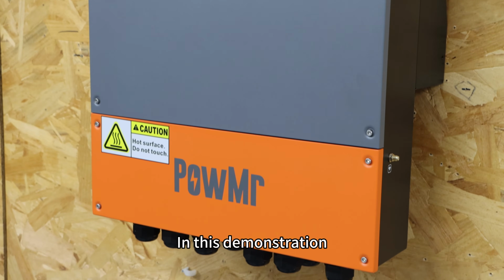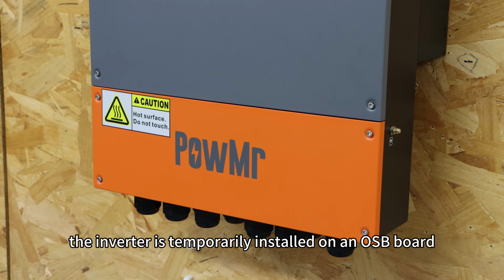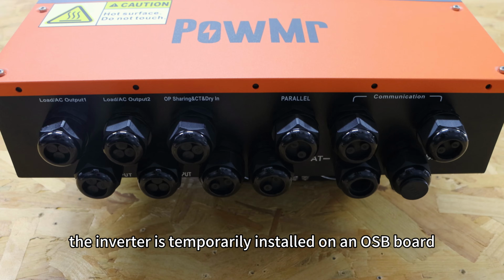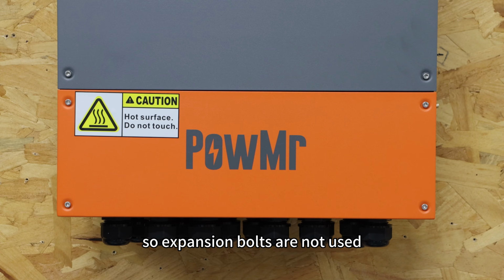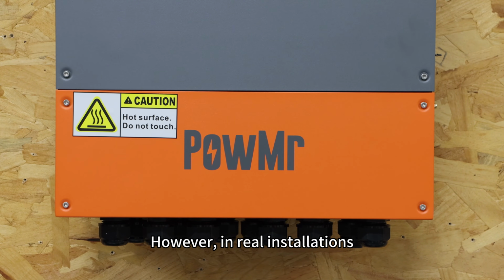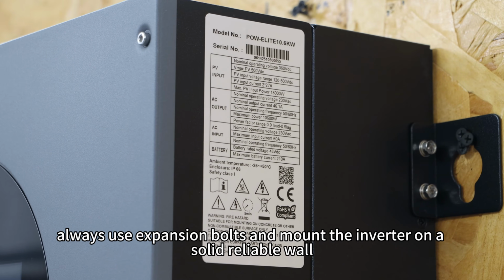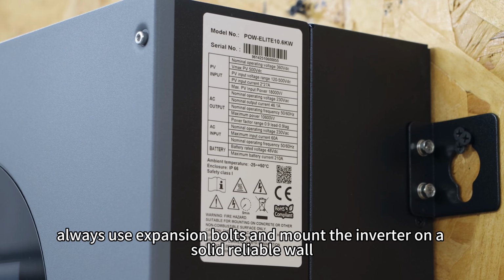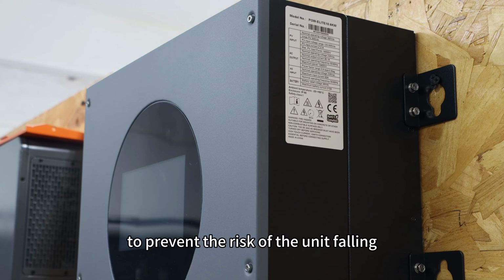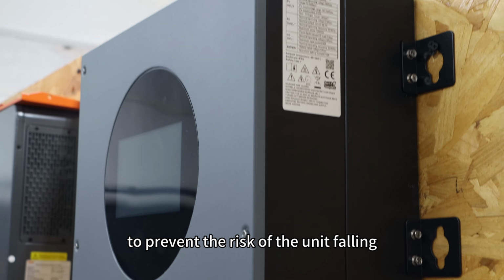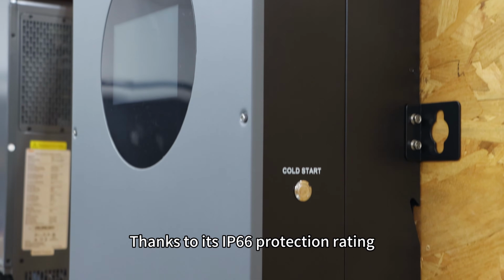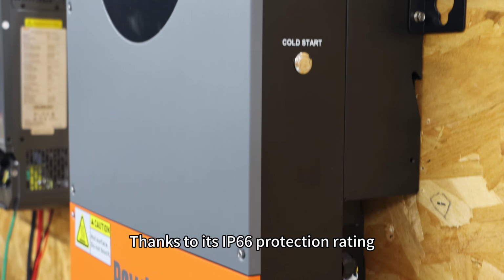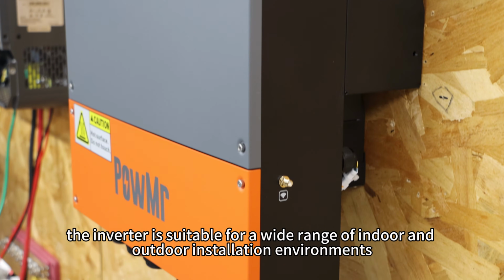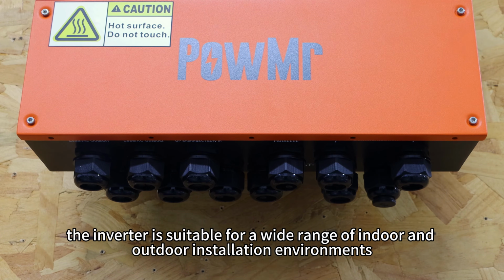In this demonstration, the inverter is temporarily installed on an OSB board, so expansion bolts are not used. However, in real installations, always use expansion bolts and mount the inverter on a solid, reliable wall to prevent the risk of the unit falling.